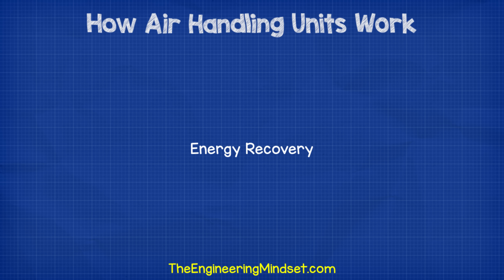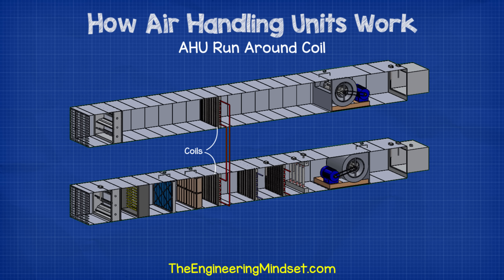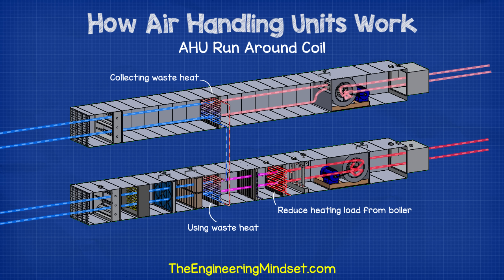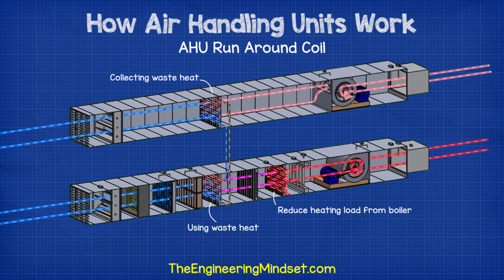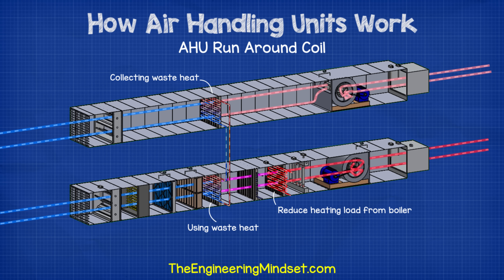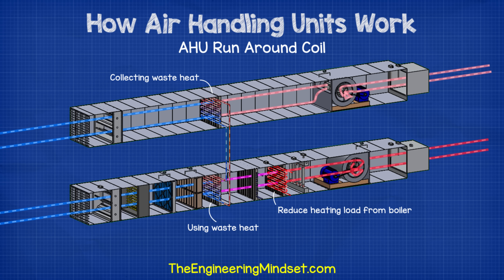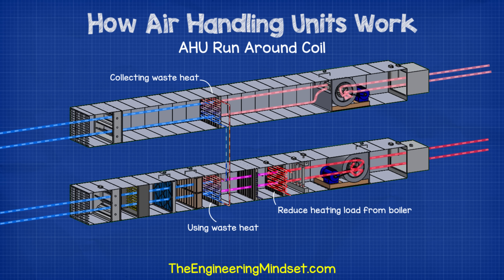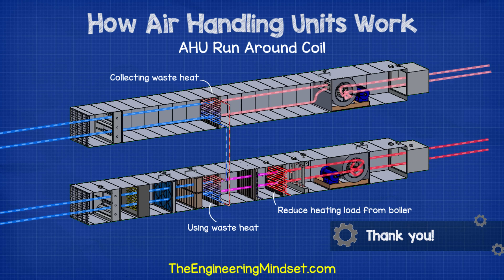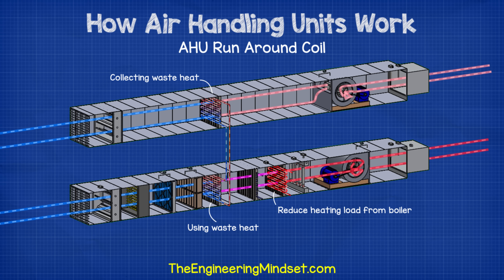Energy recovery. If the supply and extract AHUs are located in different areas, a common way to recover some of the thermal energy is to use a runaround coil. This uses a coil in both AHUs, and a pump circulates water between the two. This will pick up waste heat from the extract AHU and add it to the supply AHU, reducing the heating demand on the heating coil when the outside air temperature is below the supply set point and the return air temperature is higher. The heat would otherwise be wasted as it is simply rejected to atmosphere. As the pump consumes electricity, it is only cost effective to turn on if the energy saved is more than the pump will consume.